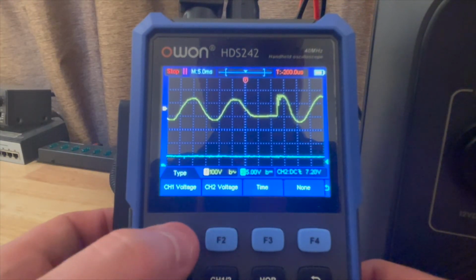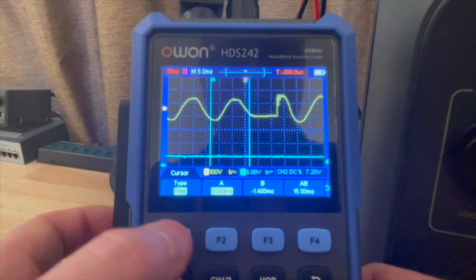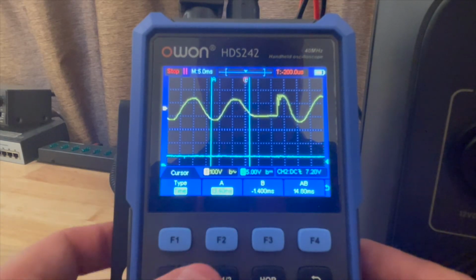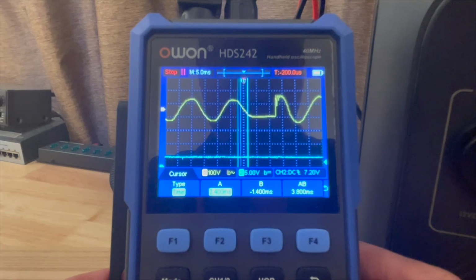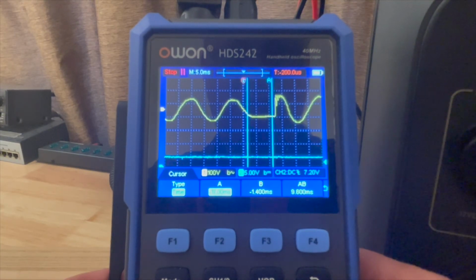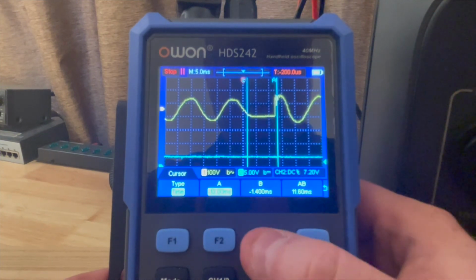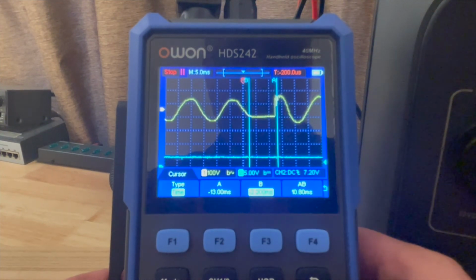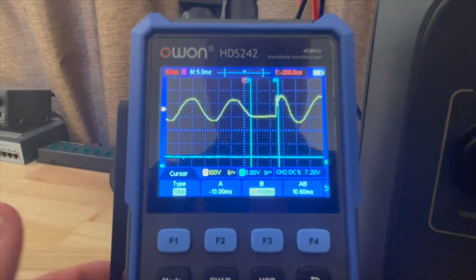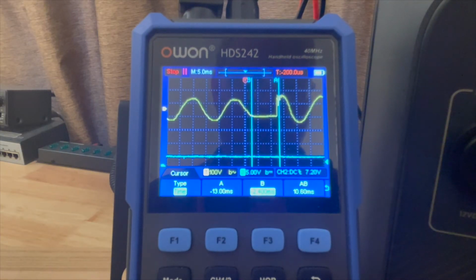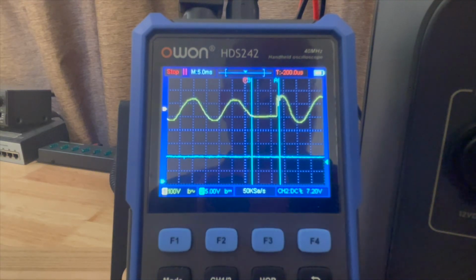Measure, cursor, type, time. Move cursor A to about there, that's pretty close. And cursor B about there-ish - so that was about 10.6 milliseconds right there. The standard is anything less than 20 milliseconds is good. Now, there will be some randomness in these measurements, so I got 10.6 right here.